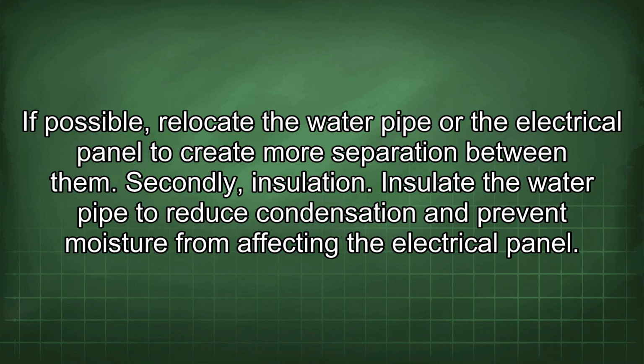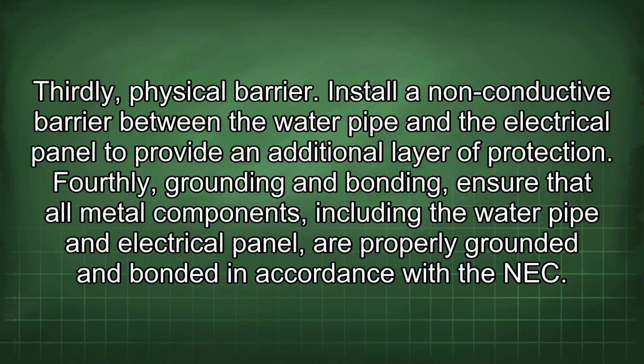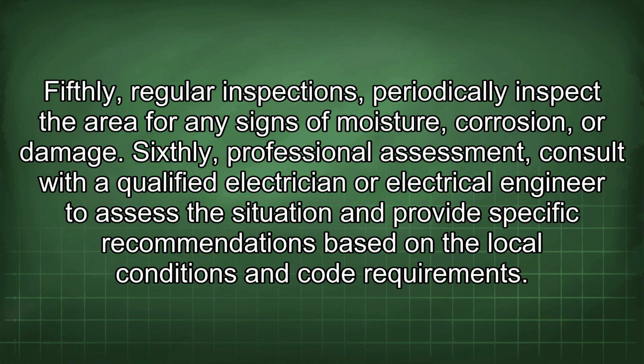Secondly, insulation. Insulate the water pipe to reduce condensation and prevent moisture from affecting the electrical panel. Thirdly, physical barrier. Install a non-conductive barrier between the water pipe and the electrical panel to provide an additional layer of protection. Fourthly, grounding and bonding. Ensure that all metal components, including the water pipe and electrical panel, are properly grounded and bonded in accordance with the NEC. Fifthly, regular inspections.